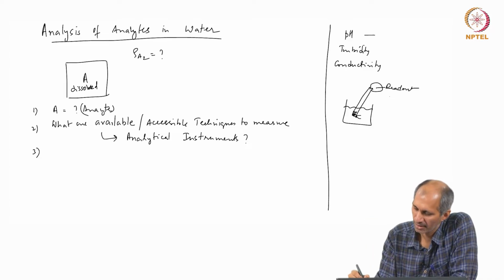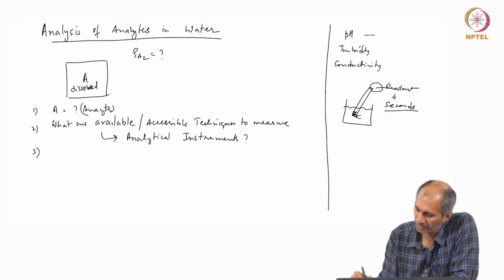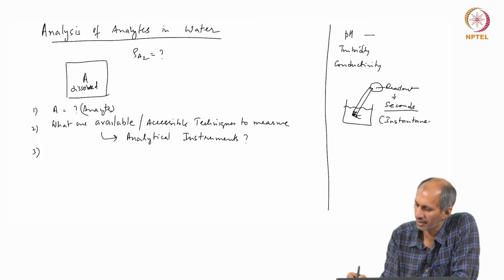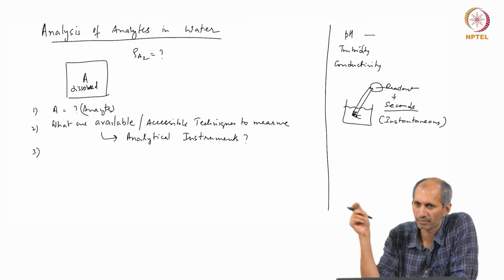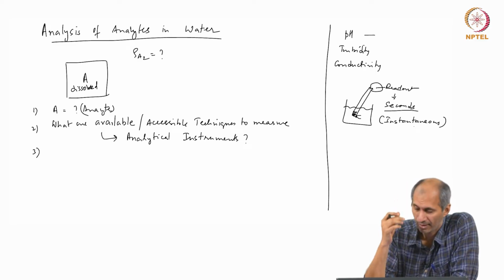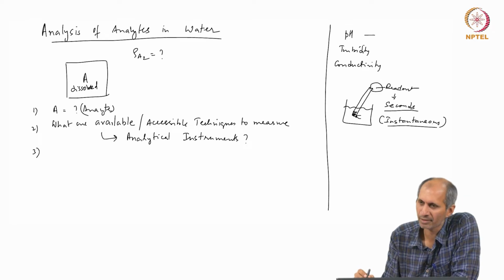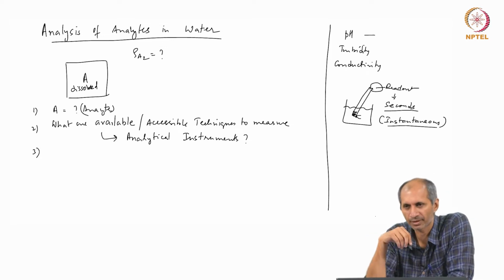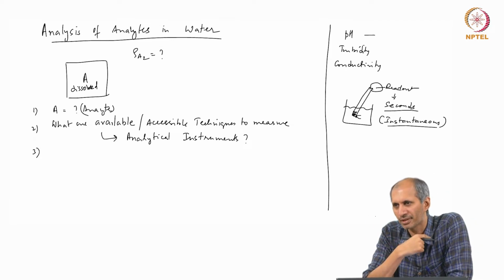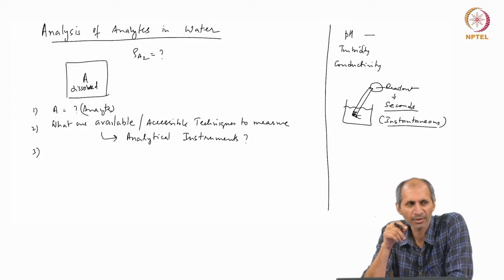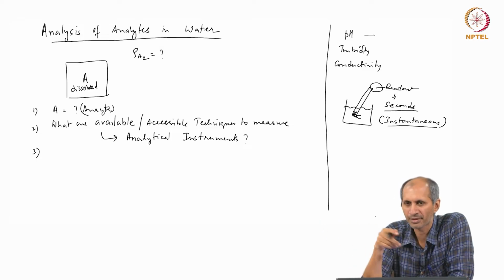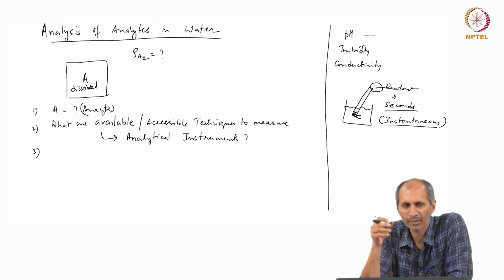Just a few seconds, on the order of seconds. So this gives what is called an instantaneous measurement, I dip it in and the reading comes out straight away. This is very useful, ideal really, because now I have the freedom to do a lot of things. My sampling objectives can be very vast. I can observe pH change over a long period of time, or over very short time scales, even if the process is happening very quickly, I can still measure the change in pH.